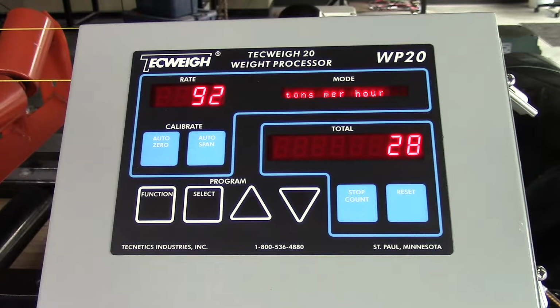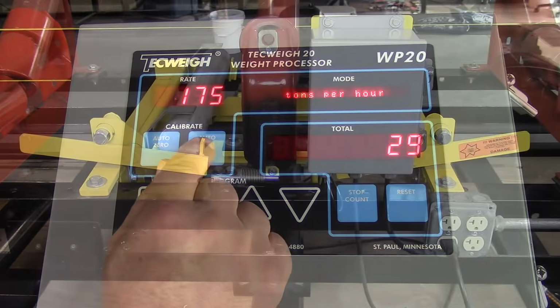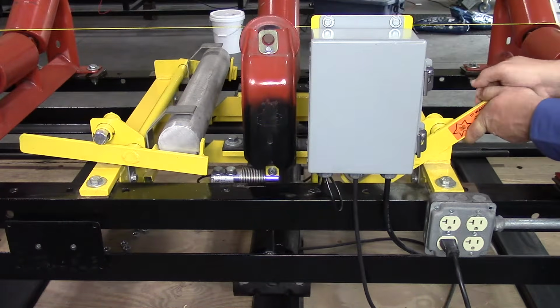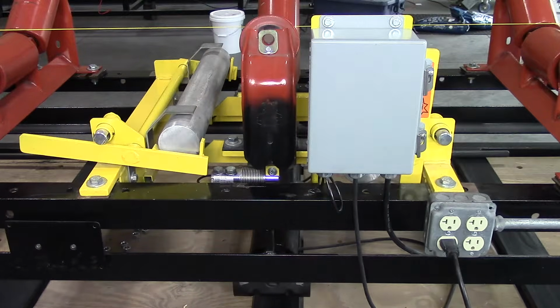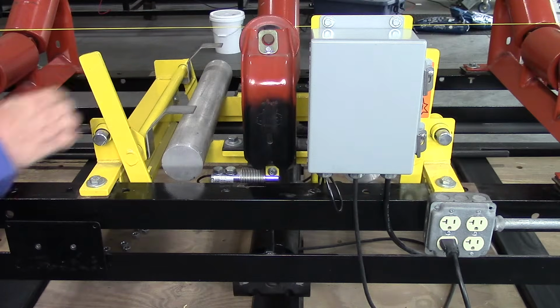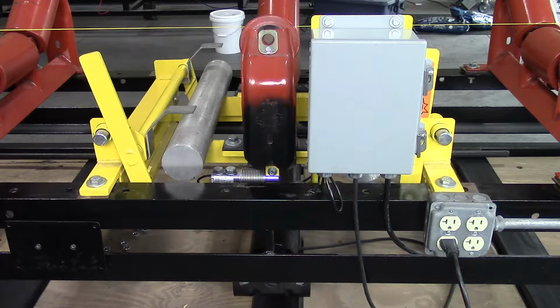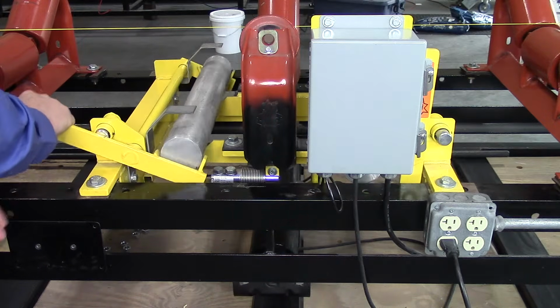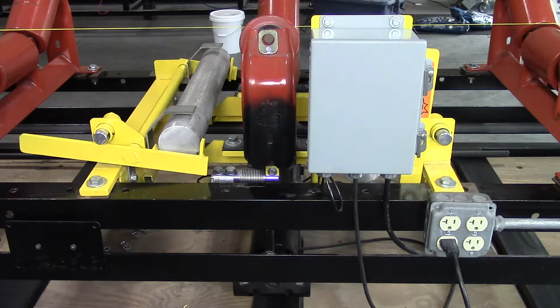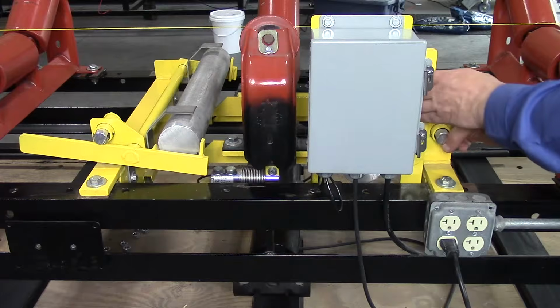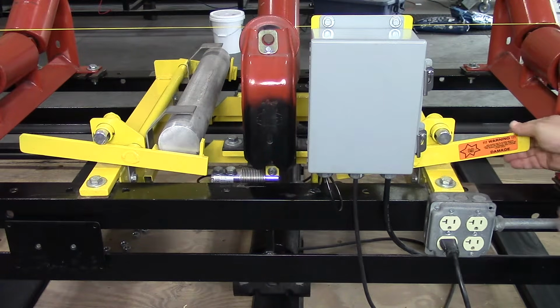I put the weight on there again just to make certain that it's showing what we expect it to. It should come up to around 170-ish in that neighborhood. It's just a good double check to make sure everything's working properly. And here I'm just going to apply the calibration weights so that way you can see what this looks like. I've added one weight, and then I'm going to add the second weight. Make sure you take all appropriate safety precautions in working around conveyors. So I've removed the weights, and then after the calibration is done, I lift the weights just like this. It's truly that simple.